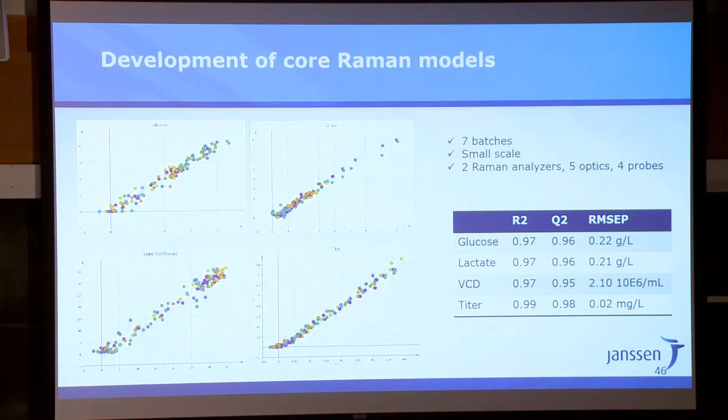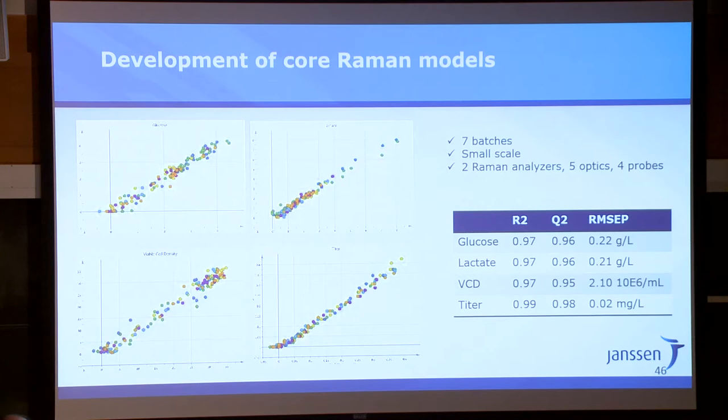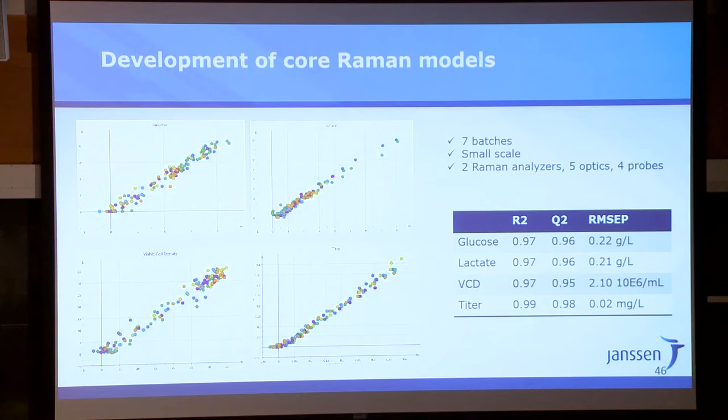We can use Raman for a number of other measurements — viable cell density, titer, various metabolites. These are things you wouldn't even think you can do with Raman, which is more than just a chemical fingerprint. The errors are very small — this is really a very robust measurement. Using that now more and more for control, the key one is glucose. Traditionally you give it a shot of glucose every day whether it needs it or not, and you see the trace of glucose with surprising variability.